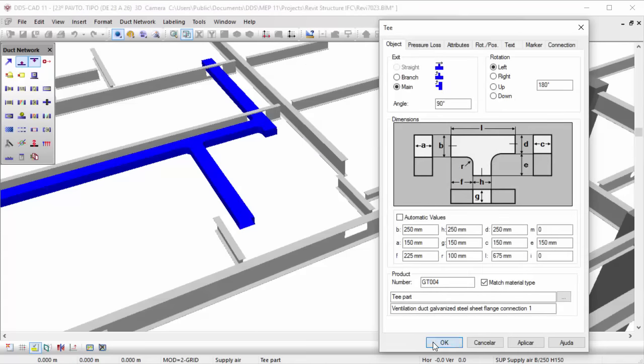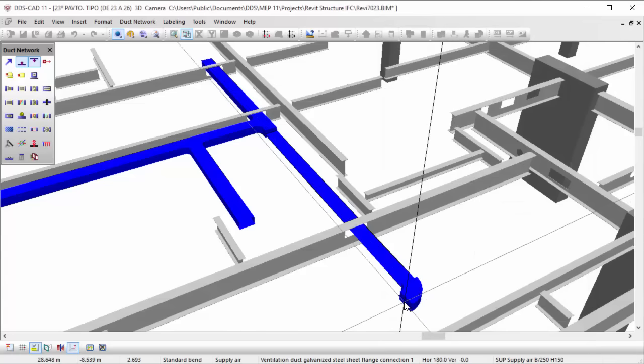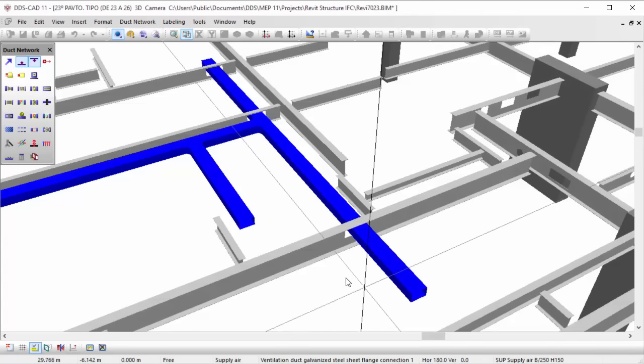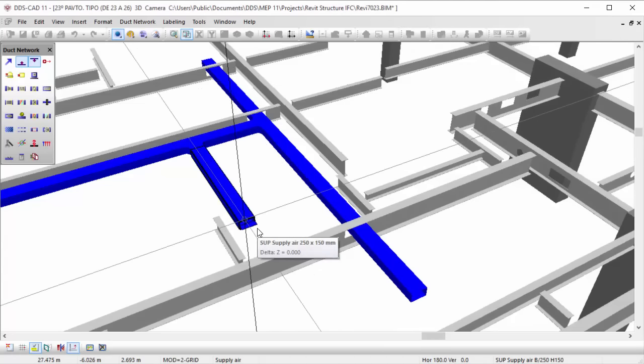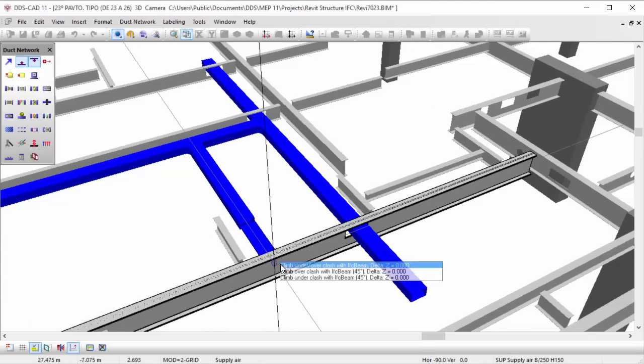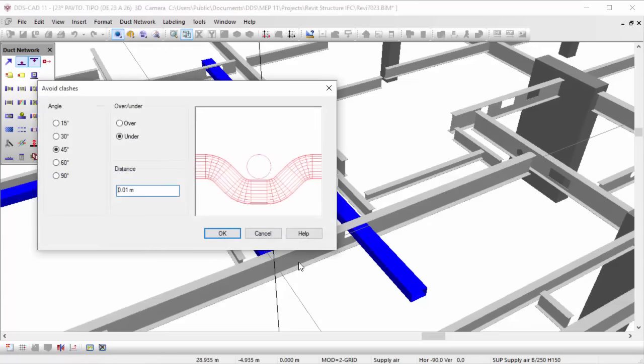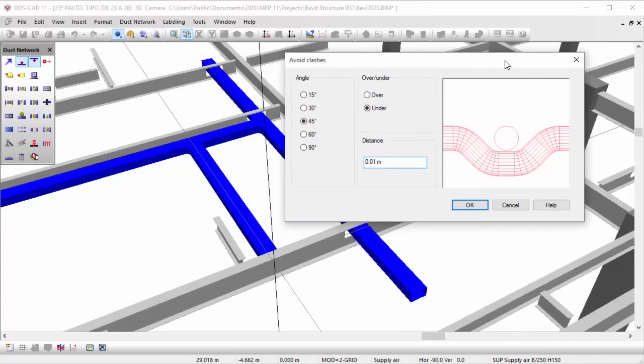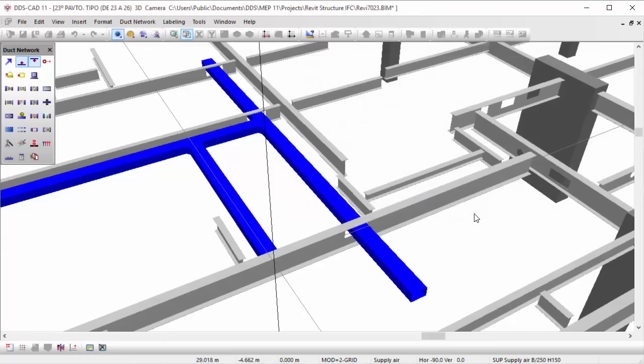A great advantage as opposed to the traditional 2D coordination of trades. Even better, DDS-CAD also provides a real-time clash prevention function when modeling MEP systems. It automatically recognizes the IFC beam in this case, providing you the option to either go under or climb over the beam to prevent the clash.